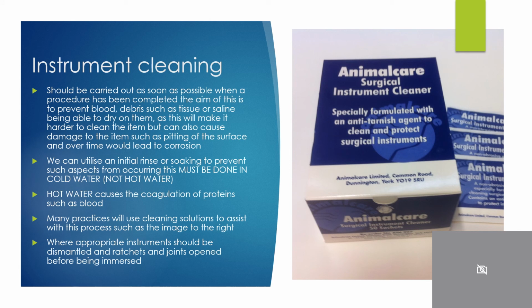Instrument cleaning should be carried out as soon as possible when a procedure has been completed. The aim of this is to prevent the blood and debris such as the tissue or saline being able to dry on them, as this will make it harder to clean the item, but can also cause damage to the item such as pitting of the surface, and over time would lead to corrosion.